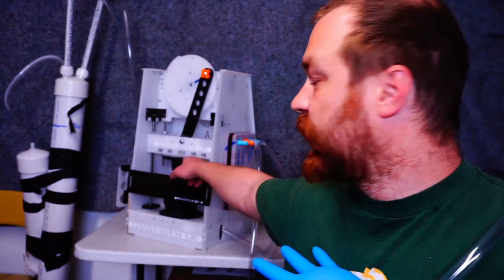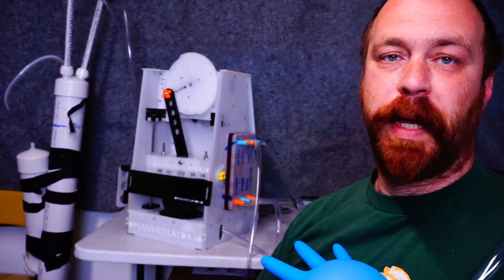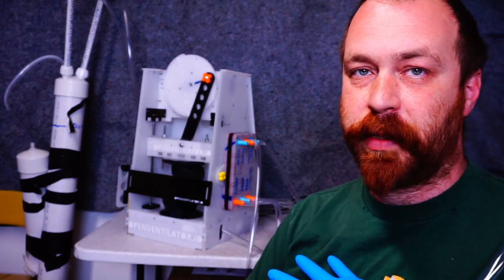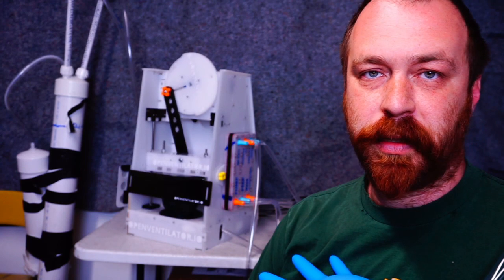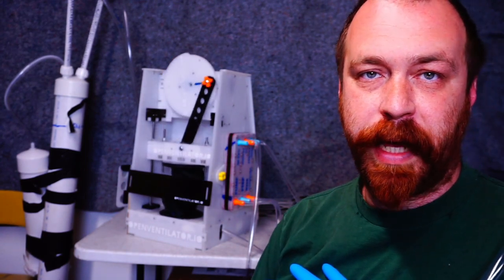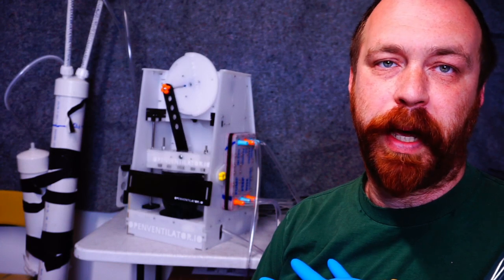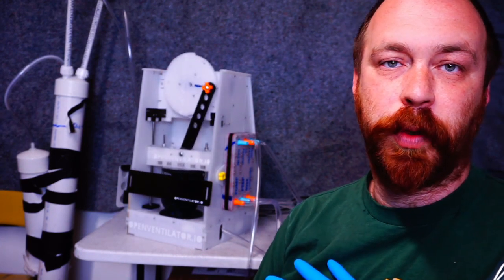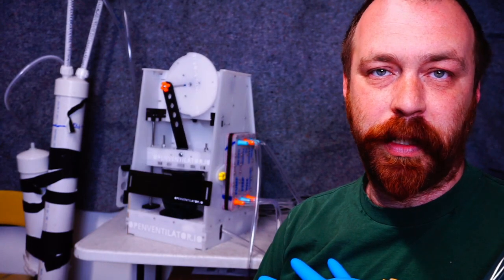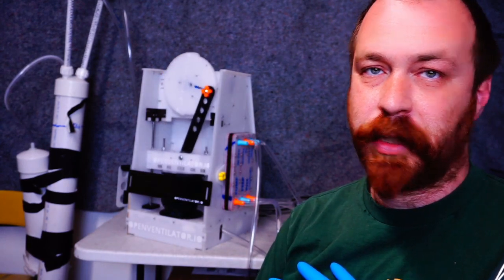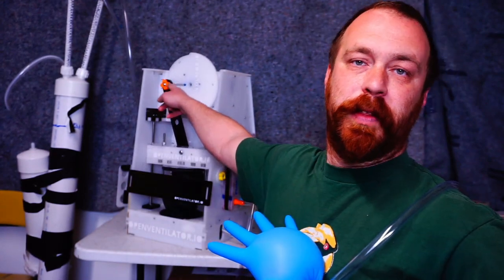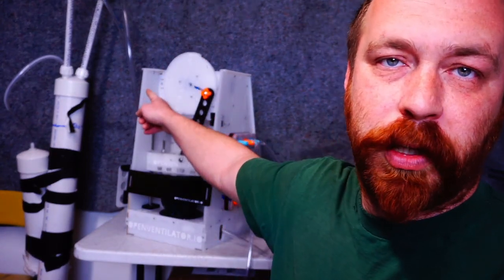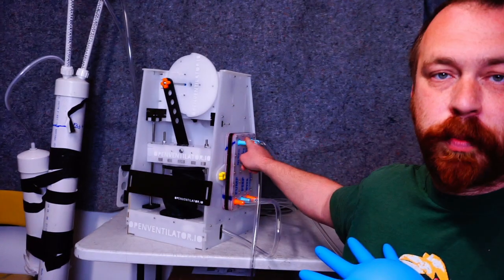For example, we're using an inner tube from a truck tire as a bellows instead of an ambu bag. This could be replaced in an industrial manufacturing situation with a silicone cast bellows or even an ambu bag if available. Likewise, there's a few 3D printed parts that are not necessarily medically sound in terms of sterilization, like this little knob over here on the volume setting control. That knob also could be laser cut, injection molded, or just removed, and you could use a pliers to tighten the nut. Also, these ports on the compound valve block are 3D printed just for convenience.